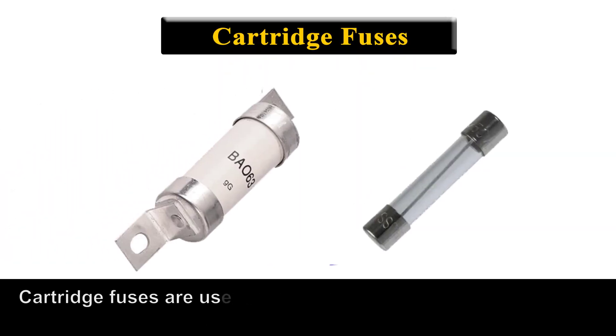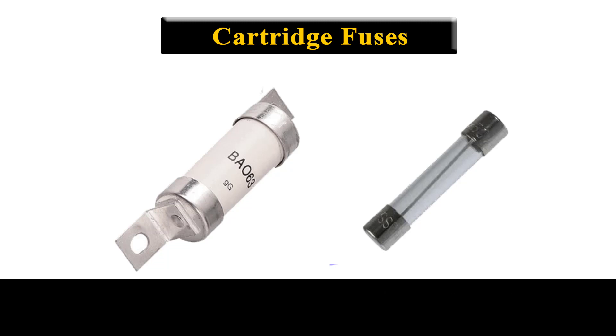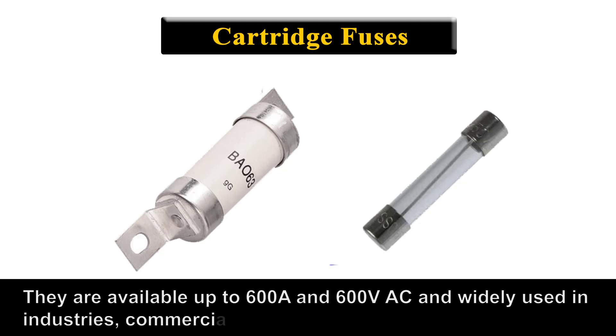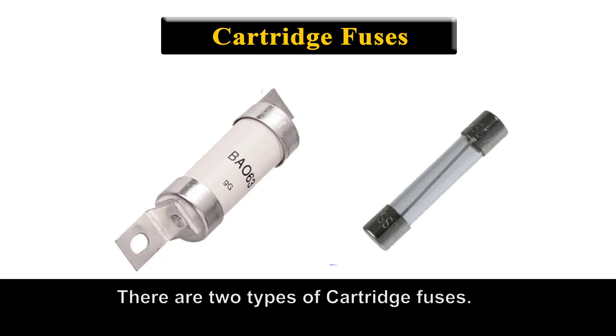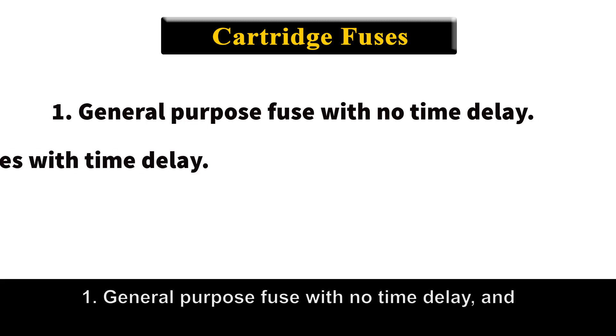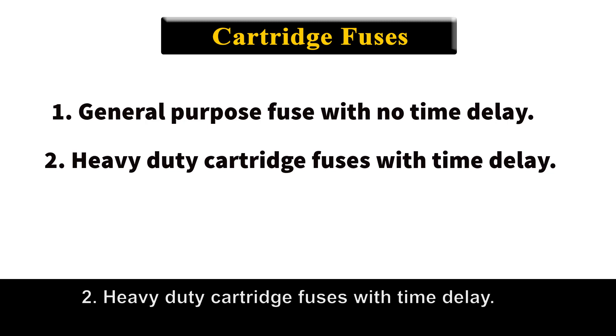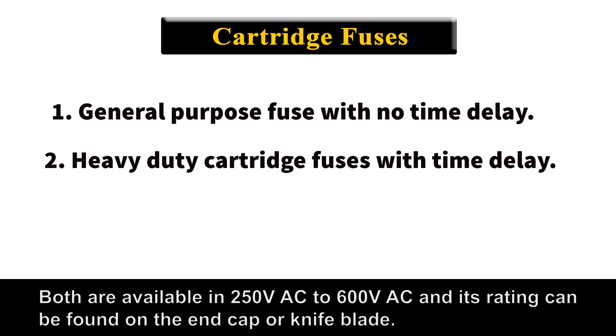Cartridge fuses are used to protect electrical appliances such as motors, air conditioners, refrigerators, pumps, etc., via high voltage ratings and currents. They are available up to 600A and 600V AC and are widely used in industries, commercial, as well as home distribution panels. There are two types of cartridge fuses: general purpose fuses with no time delay, and heavy duty cartridge fuses with time delay. Both are available from 250V AC to 600V AC and their ratings can be found on the end cap or knife blade.